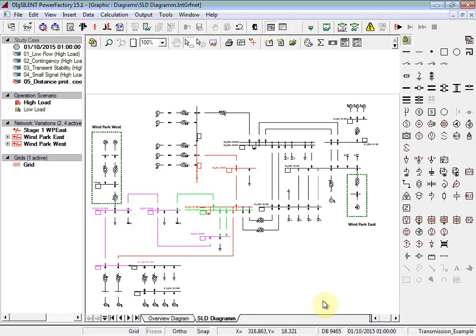Here you can see the paths. Paths are used to define coordination paths along which the coordination of the different relay elements can be examined. The Distance Protection Coordination Assistant can be provided with these paths and can automatically calculate the zone reach settings for each of the elements contained within that path. Let's start the Distance Protection Coordination Assistant.